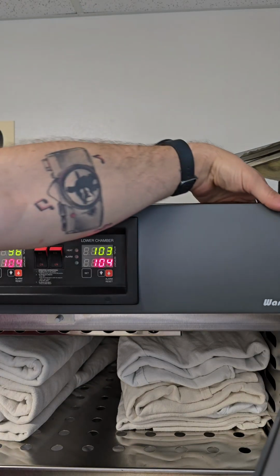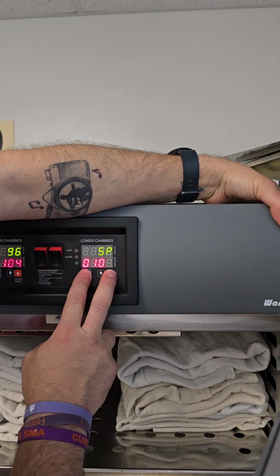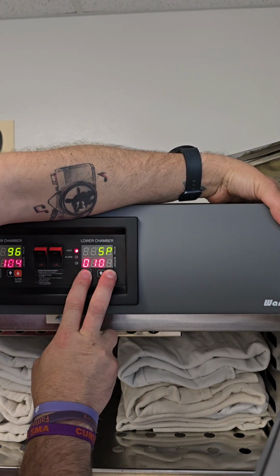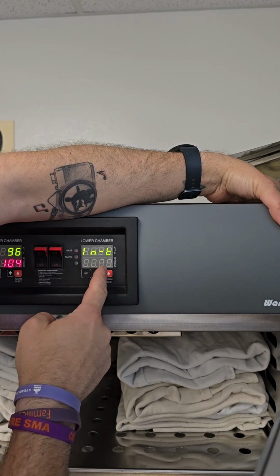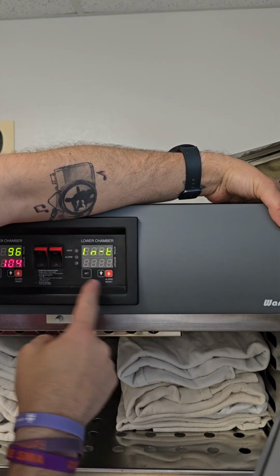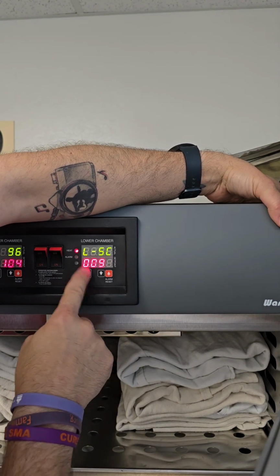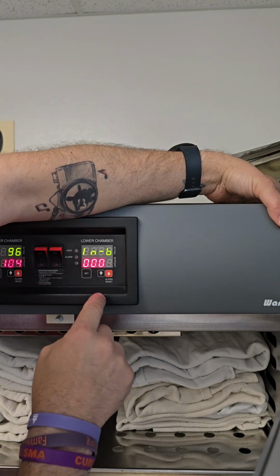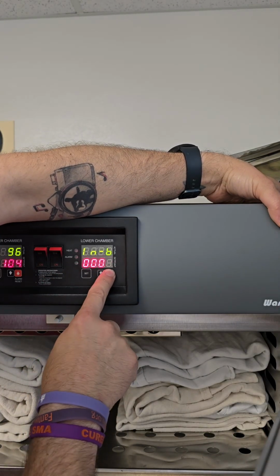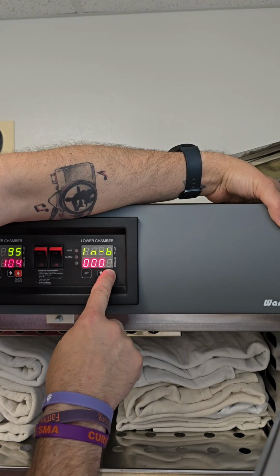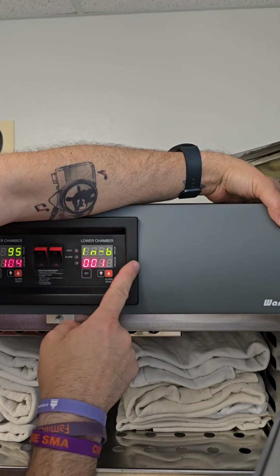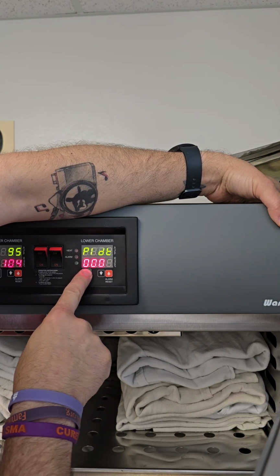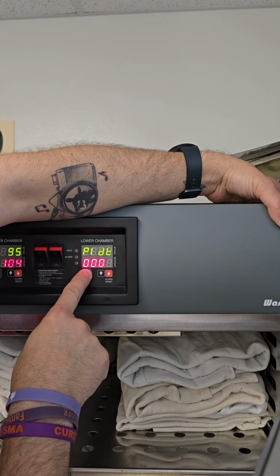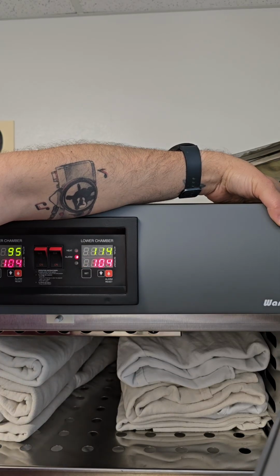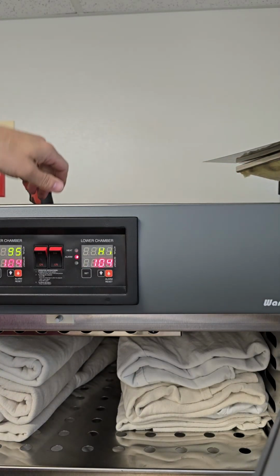So I'm going to hold the inside button, press both of these. 1, 2, 3. There's the window we're looking for. Continue holding the inside button. Just press set until you get to that one. I said we're off by 10, so we're going to go up 10 times. There we go. Press and hold set for about 3 more seconds till it goes back. There we go. Let go.